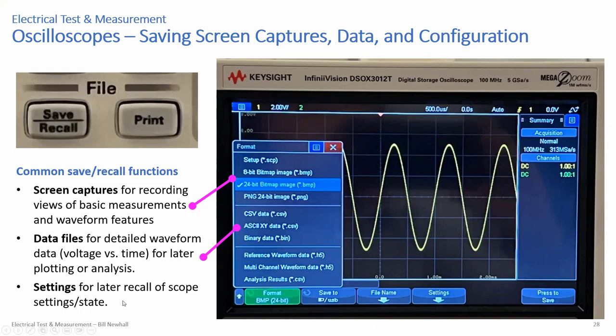You can also save scope settings for later recall. If you've set a specific trigger, vertical span, horizontal span, scale, and measurement functions, you can save all of those settings to a USB stick. Later you don't have to repeat all those button presses. This is especially useful for demonstrations: if a customer shows up, just load the saved settings and do your demo.